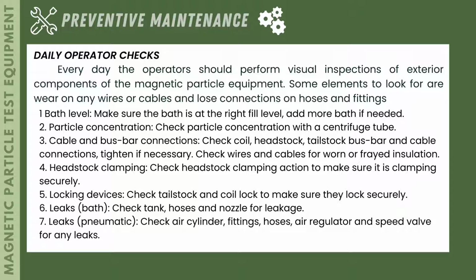Second is the particle concentration. Check particle concentration with the centrifuge tube. Third is the cable and bus bar connections. Check coil, headstock, tailstock bus bar, and cable connections. Tighten if necessary. Check wires and cables for worn or frayed insulation. Fourth is the headstock clamping. Check headstock clamping action to make sure it is clamping securely. Fifth is the locking devices. Check tailstock and coil lock to make sure they lock securely.